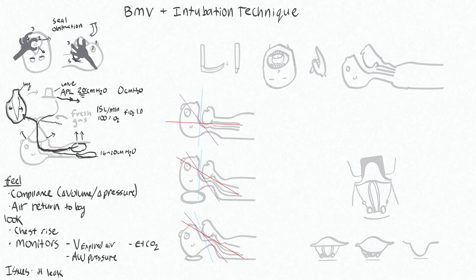Make sure that you have set this to an appropriate number. You'll actually have to turn this up because when you're having the patient breathe spontaneously before, it's more comfortable for them to breathe when there is no pressure in the circuit. So you'll actually have it on zero. If you don't remember to change it to something like 20 when you go to give them positive pressure, then it might seem like there is a leak in your circuit. So that's issue number one.